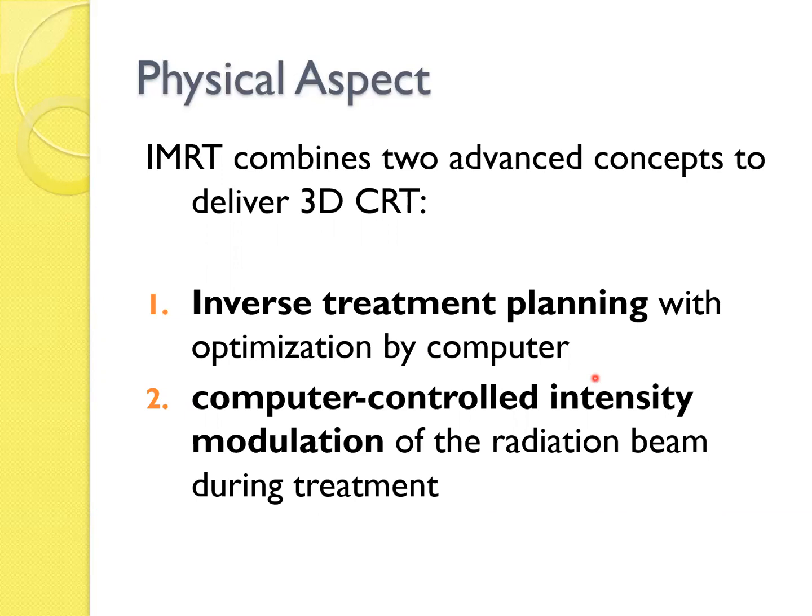So the physical aspect, IMRT combined two advanced concepts to deliver the 3D CRT. The one is inverse treatment planning with the help of optimization by computer and the computer control intensity modulation of the radiation beam during the treatment, that is with the MLCs.